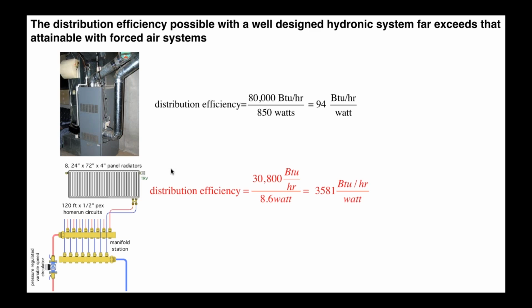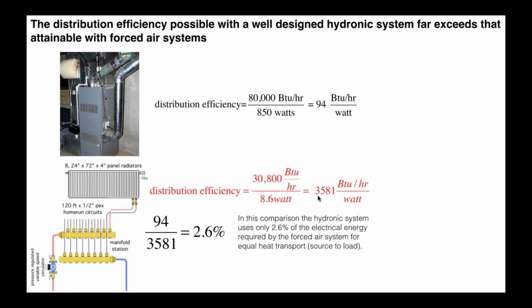All right, so let's make a comparison. Let's compare that furnace, 80,000 BTUs per hour, requiring 850 watts. So we had 94 BTUs per hour per watt, compared to what we just looked at. And again, look at the ratio of those two distribution efficiencies. What this is saying is that the hydronic system, this specific, well-designed, state-of-the-art hydronic system, is delivering heat using about 2.6% of the electrical input power compared to that older generation furnace system. This is a huge inherent advantage of hydronics, regardless of whether it's a heat pump providing that heat or a boiler or solar collectors. And it's an often undersold benefit, I'll call it.